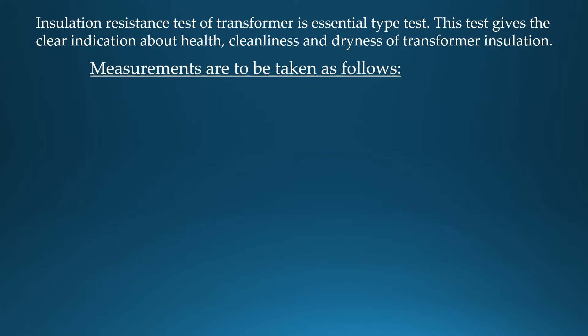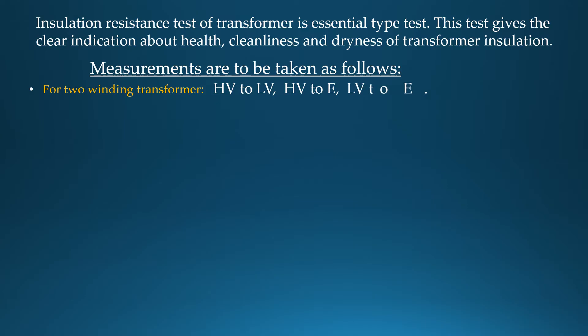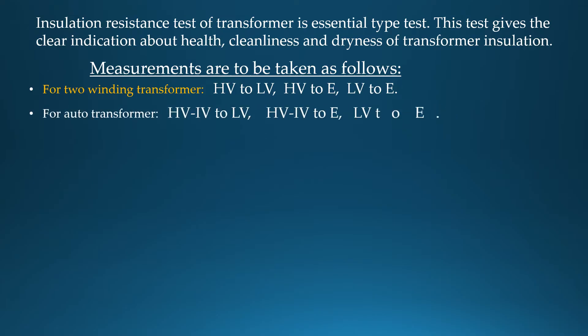Measurements are to be taken as follows. For two winding transformers: HV to LV, HV to Earth, LV to Earth. For auto transformers: HV/IV to LV, HV/IV to Earth, LV to Earth.